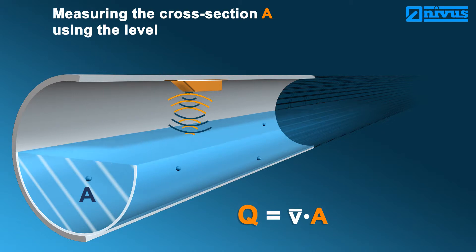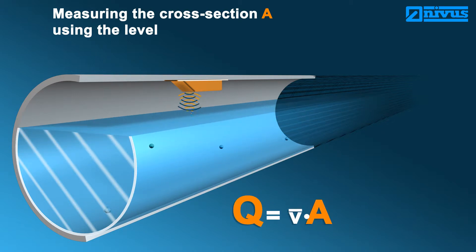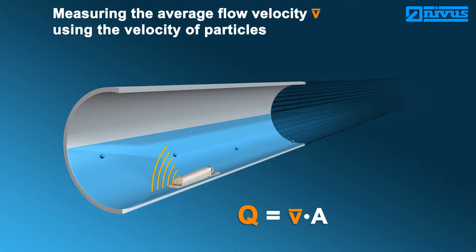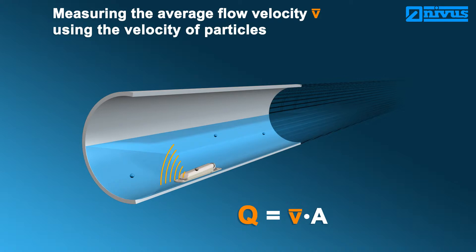The flow velocity is detected by measuring the particle velocity. Most media, particularly wastewater, contain dirt particles or gas bubbles moving with the same velocity as the medium. The velocity of the particles is measured using ultrasound. As soon as the velocity changes, the flow normally changes as well.